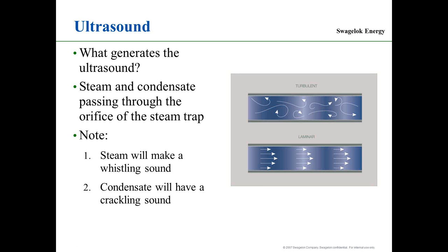Now, I'll make a note, because this ultrasound unit provides you the ability to listen to the high-frequency by heterodyning the ultrasound to a more audible sound. Steam will make a distinct whistling sound. Condensate will make a distinct crackling sound. So I want to tell people, when you're testing a steam trap, yes, watch the meter, but also listen.